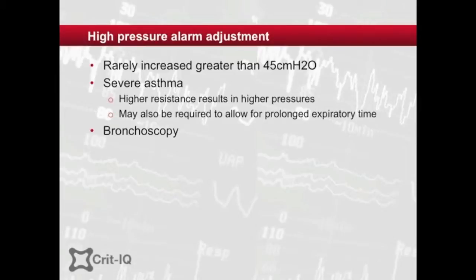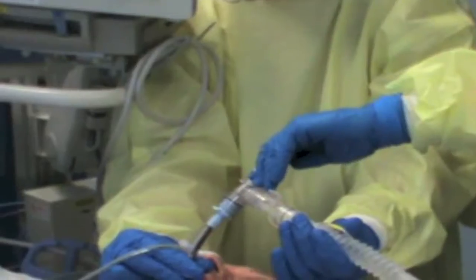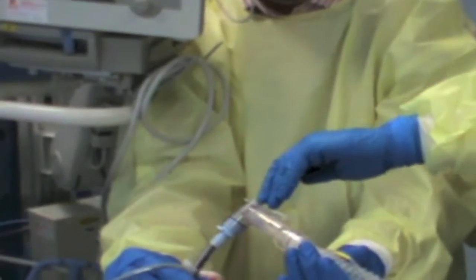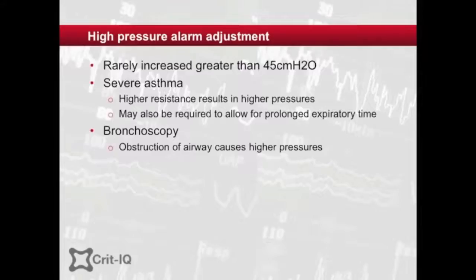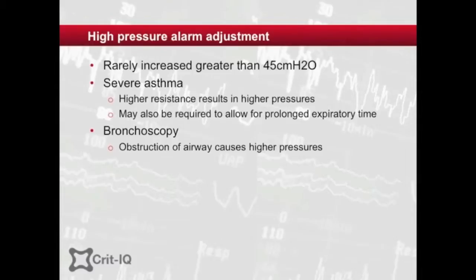The high pressure alarm is also increased when performing a bronchoscopy. The presence of the scope in the airway significantly contributes to resistance, increasing pressure in volume-controlled modes. If the pressure alarm is not increased, the ventilator will cycle to expiration, under-ventilating the patient. Care should be taken to ensure that the alarm is returned to normal after the procedure.